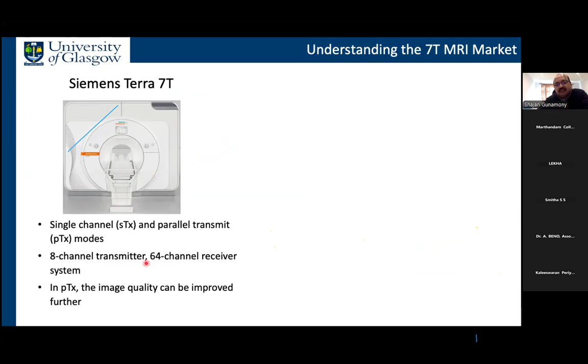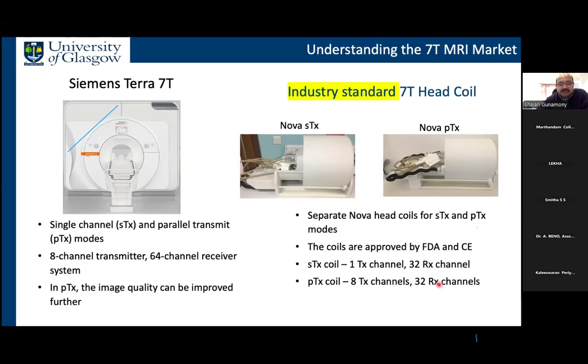So this is the Siemens 7 Tesla MRI scanner. This scanner operates in two modes. They call the STX mode and the PTX mode. And in terms of configuration, it has 8 transmit channels and 64 receive channels. And this is the current industry standard 7 Tesla head coil. They have 2 coils, one for STX and one for PTX. It's from a company called Nova in the US. And you need separate coils for these scanner modes. And it's important to note that these coils are FDA and CE approved. So that means they are approved by the regulatory authorities. But although the scanner has 64 receive channels, this coil has 32 channels. So this means we are not really utilizing the scanner to its full capability.